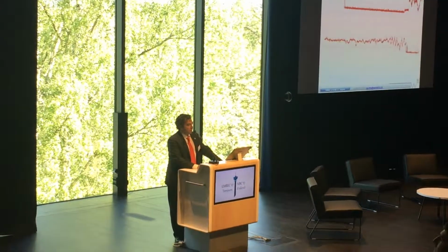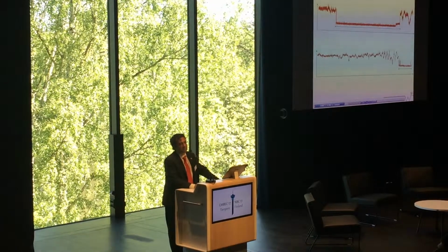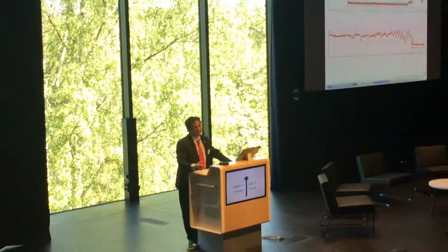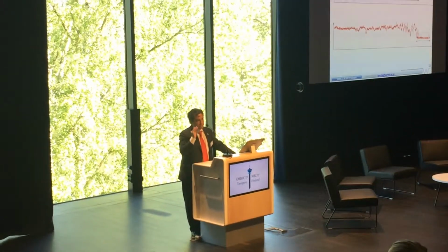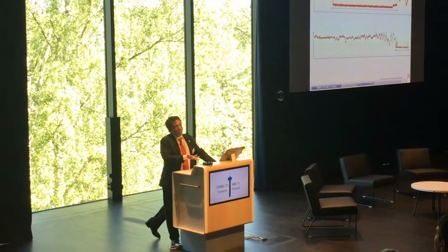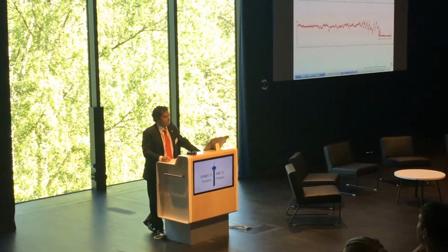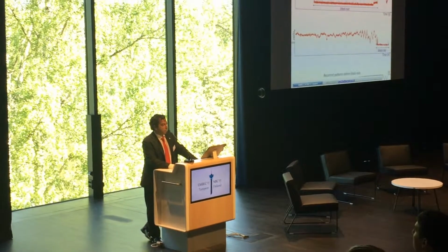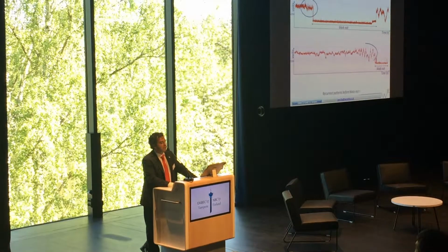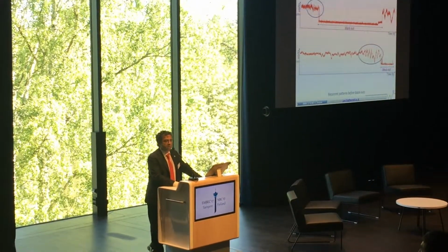This is a couple of examples of blackouts, several times a day. This is in the surgical theater, so then they replaced the inverter. As you can see, there is still continuity. And when you see the plateau, that's because the inverter is actually providing more stable power than the power supply. But look at this. Before the blackout, there are clear trends, which means that those blackouts are not casual.